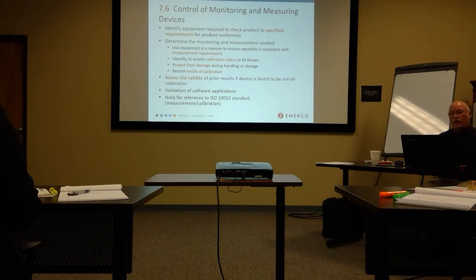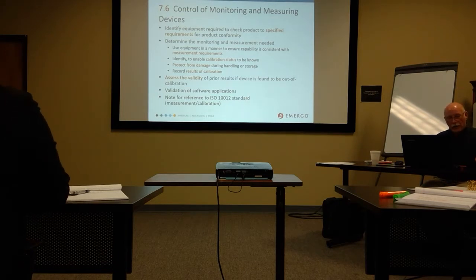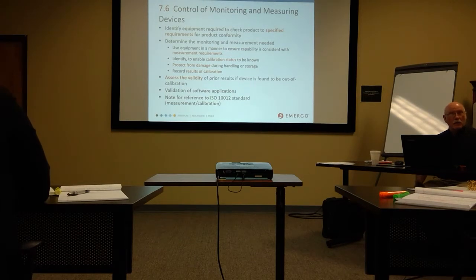They have a calibration vendor, so he brings me the certs from the vendor, and I'm looking at it and it says, as found, out of calibration. Okay. Second, as found, out of calibration. So I asked the fellow who was in charge of this, who happened to be the warehouse guy, not a good choice, I said, so what did you do? Oh, deer in the headlights look, he has no clue. He never read the certs. This calibration had been done 3 or 4 months previously, and it's an annual calibration. So for 364 days, potentially, both of these laser power meters had been out of calibration. They did not know it. They took no action because they're completely unaware of it.